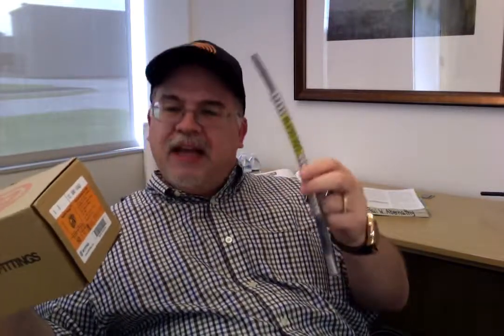Okay, so with the above ranges, it'll give you the diameters of the cable that will be provided by the manufacturer. It will tell you the range of the cable, and that's how you select the fitting. You don't simply select a fitting because you say this is a 3/8 or ½ inch or whatever. It's based on a figure that we give you at the manufacturer, the diameters, the OD, and that's how you select the fitting for use.